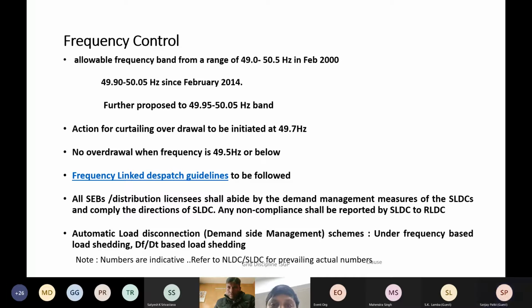Again, historically, the frequency band within which the grid has to operate has progressively become narrower and narrower. In the good old days, it used to be 47.5 to 52.5, such a wide operational band. In 2000, it was brought to 49 to 50.5. Then in 2014, it was made 49.9 to 50.05. And it is further proposed that this frequency control be narrowed down to 49.95 to 50.05. But today it is 49.9 to 50.05.